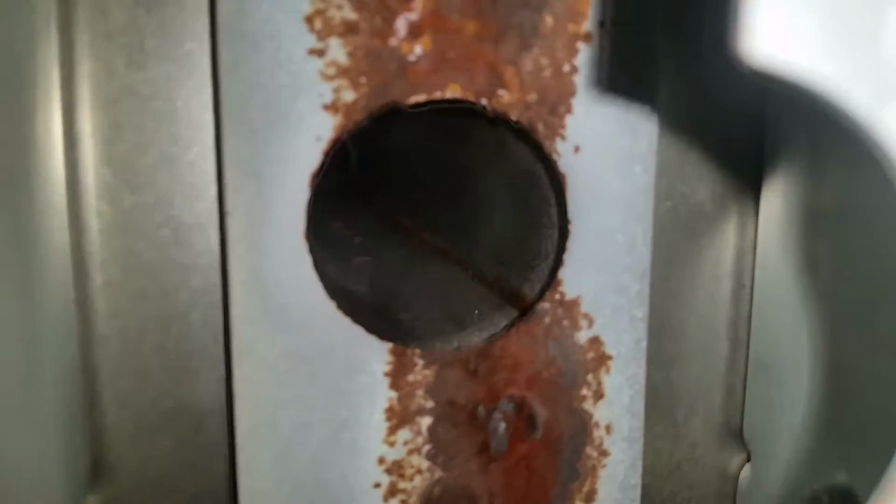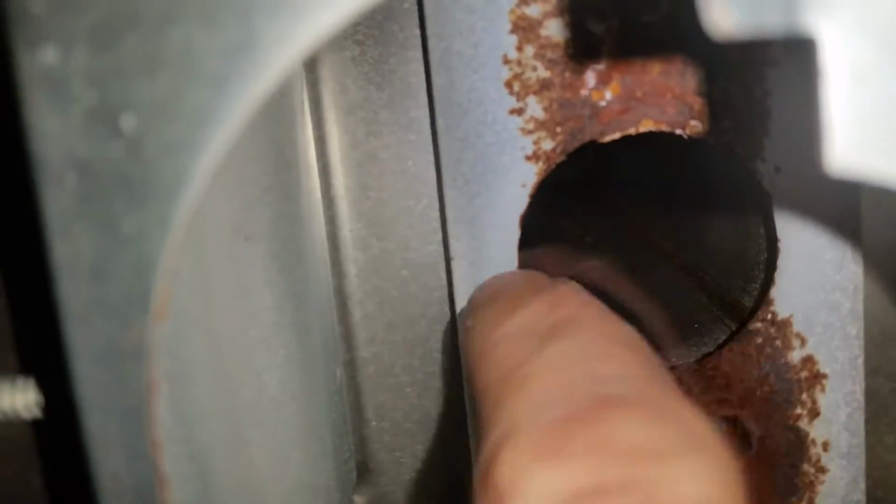Okay, we're going to try and show you the best we possibly can on these. It's kind of hard to get in there and see it, but you can see on the interior, back in there, you can see where it's already eaten through the heat exchanger, and you can see it's eaten through on this side here, especially right in this general area here. So you can see the heavy corrosion that was going on due to the improper combustion.